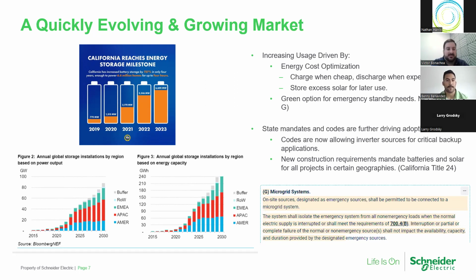So if I were just to pick some numbers right now, because it's roughly a 25% ratio, if you're buying energy at 20 cents a kilowatt hour, you're selling back maybe somewhere around 5 cents a kilowatt hour. That's usually what you see as far as that relationship. So you're actually burning basically 15 cents per kilowatt hour that you could have benefited from. So it's much better, as Benny said, to store that energy for later to use it yourself rather than sell it back to the utility, which is really not going to pay you a fair rate for it to some extent. So that's one of the drivers behind energy cost.